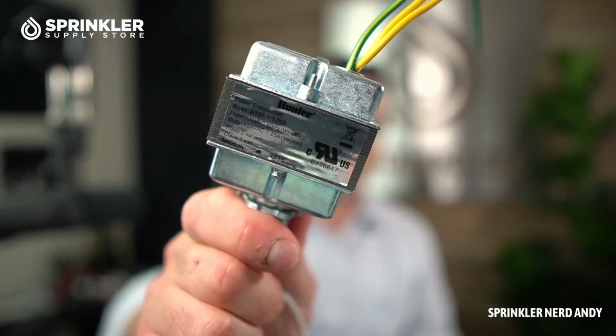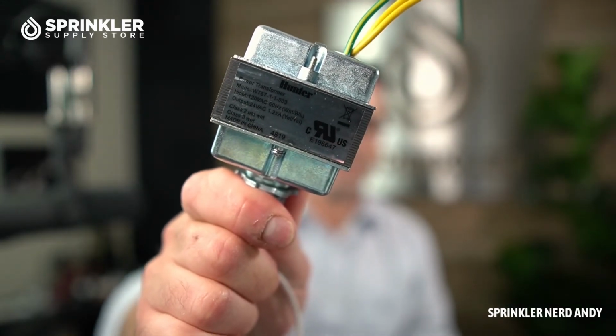And again, I've been on projects when I was traveling, working for Baseline, where I'd come up to some sites that would have a failed transformer. And if you need to fix it that day, you can source transformers from electrical supply houses and make the replacement. Because the only thing that makes this a Hunter transformer is what? The sticker. That's the only thing that makes this a Hunter transformer, the sticker and the specifications. Otherwise, for the most part, transformers are transformers. They take 120 volts or 110 volts or 122 volts, whatever it might be coming in, and reduce it down to 24 volts or a multiple of that incoming power. And that's all it does, transforms the power.